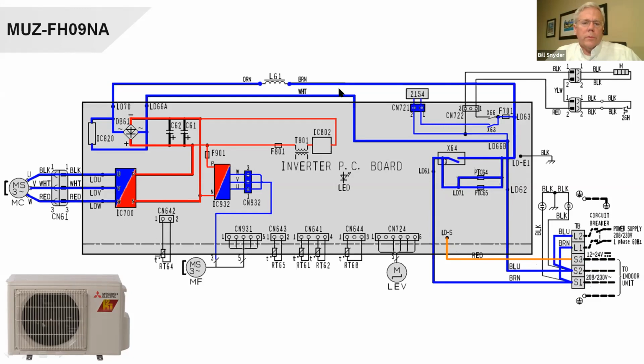And we've got the noise filter in here. This L61 happens to be that reactor that looks like the transformer. Again, this time it's on the AC side. It comes in here to this device that converts it from AC to DC. Again, you see the little AC sine waves there, and a minus and a plus here. This comes out, and some of the voltage goes over here to the intelligent power module that converts it back to 3-phase AC, and some of it comes over here, and we are feeding U, V, and W directly here with 3 wires to this outside condenser fan motor.